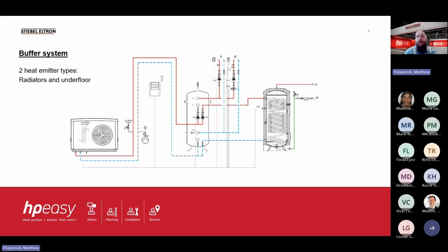We have our energy source and our volume, and then we have two individual loading stations to be able to extract the energy from the buffer at the determined temperatures, so 45 and 38, without causing any problems to either heat emitter. Now, the reason we do this, underfloor and radiator heat emitters have different flow rates. And if the flow rate passes through a heat emitter too quickly, there is not enough time for the heat to be deposited or delivered into that room or the area. So it's just speeding through the system and returning back to the cylinder, which can then cause faults or problems with the air source heat pump, because it's a natural balance. The heat pump is loading the buffer with temperature, and the heat emitters are extracting the temperature from the buffer. If there is no extraction, the heat pump will overheat the buffer cylinder and then switch off in a fault. So that's the main reason why you would normally have a buffer cylinder with two separate heat emitter types for that hydraulic separation. Now, buffers can range in various sizes, so this diagram is just an example. They're not normally as large as these tanks.